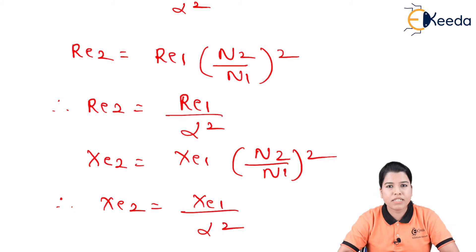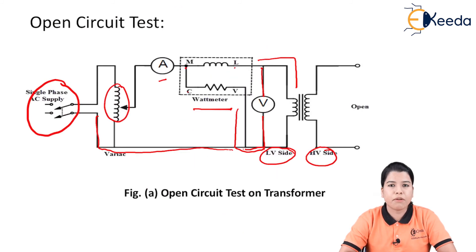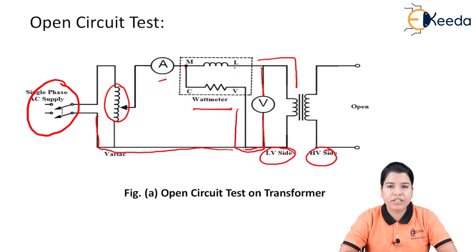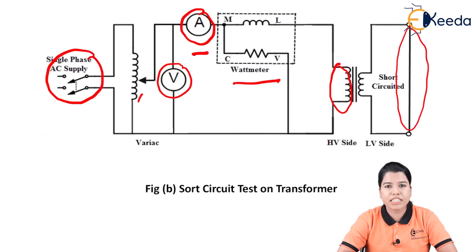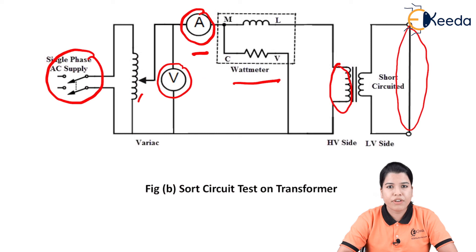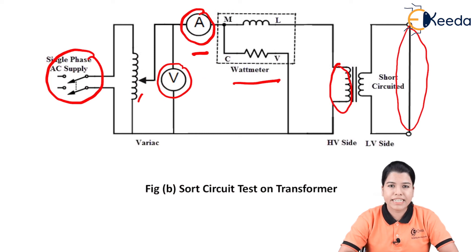In the open circuit test, the supply is given to the LV winding while the HV winding is kept open. This is because laboratory instruments can measure the low voltage of the LV winding, whereas instruments to measure the high voltage of the HV winding are not readily available. In the short circuit test, the supply is given to the HV winding while the LV winding is short circuited, because the HV winding carries less current than the LV winding, and only a very low voltage is needed to achieve rated current.